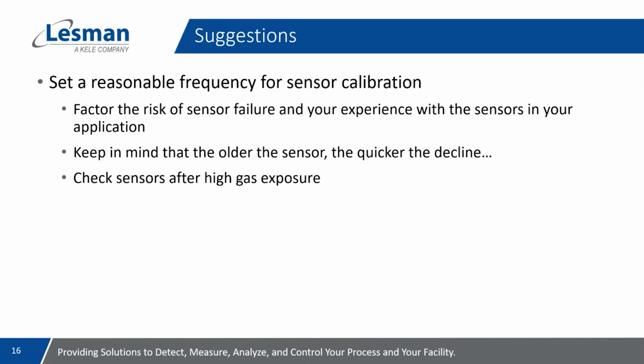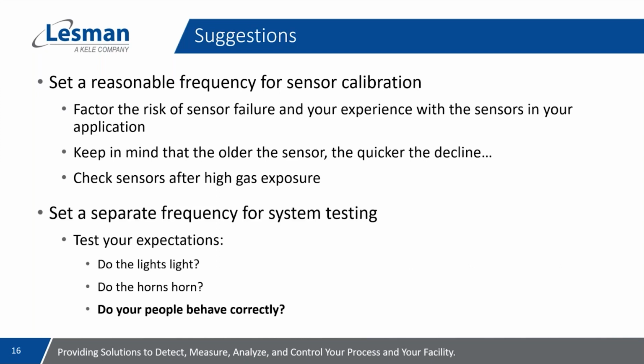The other habit to consider is to check your sensor and system after any high gas event. Make sure nothing got damaged or exceedingly aged from the exposure to the gas. Confirm the system still works as expected. And if the employees respond as expected, make sure to encourage and applaud that behavior. Finally, I'd suggest that separate from the sensor calibration and maintenance work, that you set some interval to do full system testing, right down to the employee level, right down to the behaviors. This is the biggest area for potential improvement in most industrial gas systems that I see.